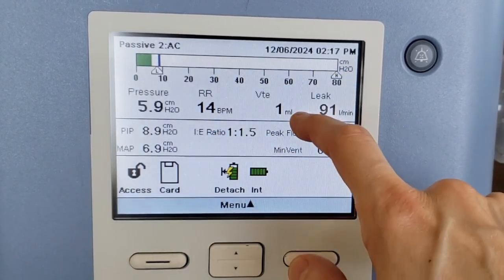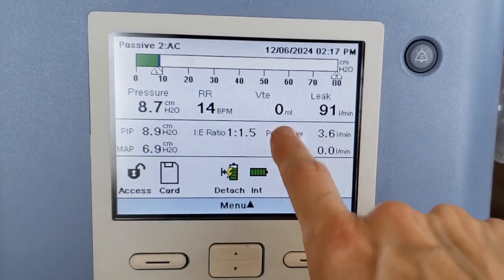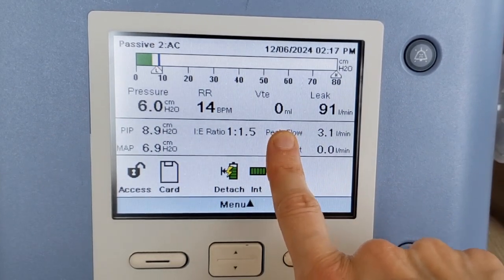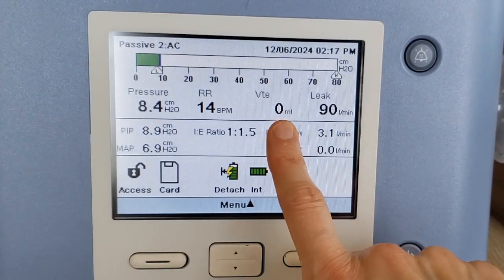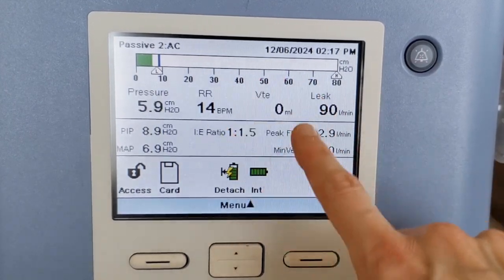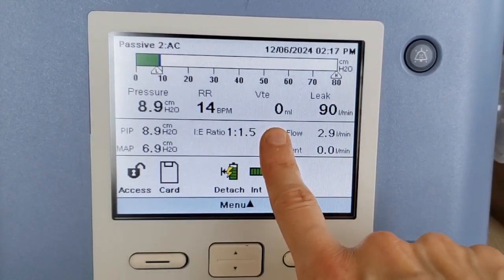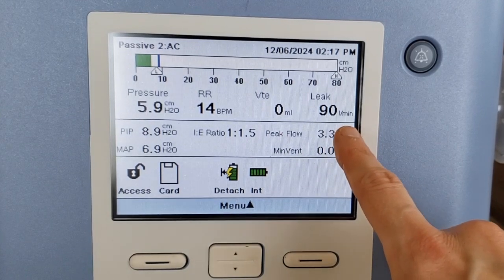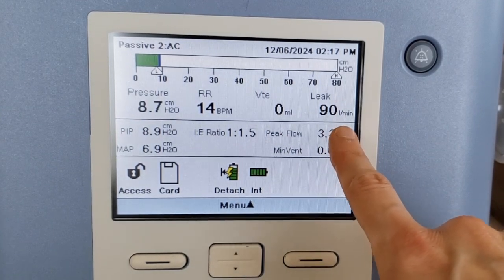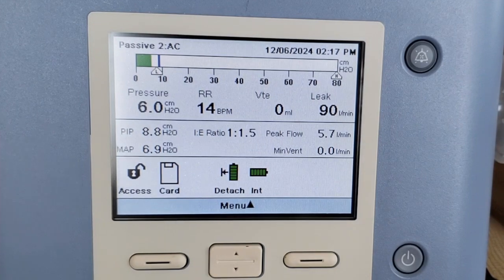And then the volume total exhaled. I do not actually have this machine connected to me because I'm using my other machine to be able to film this. And this should not be at 0. This should be a higher number. And then this is the leak. The leak is really high right now because I do not have the machine on. But let me switch over quickly to the machine.